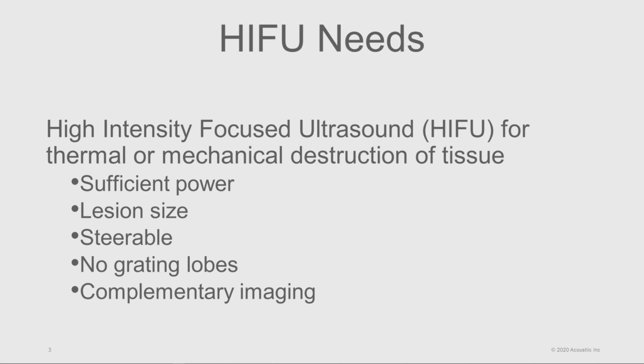Controllable and reliable lesion size and shape are also necessary to accurately destroy target tissue with minimal margins. Higher frequencies allow for smaller lesions, but suffer from increased attenuation in the body, reducing penetration and causing heat deposition in intervening layers. A wide area of transmitting surface, both in elevation and azimuth, ensures control over F number and lesion lateral dimensions. Finally, a large number of individually controlled elements leads to the ability to beamform, steering the beam either simply to a point or with appropriate calculations to correct for tissue aberration.